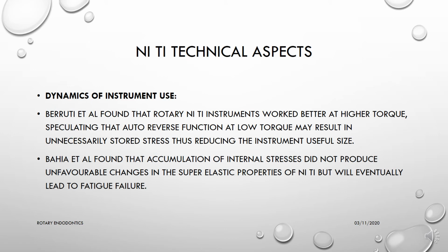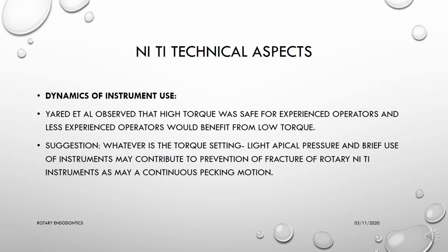Berruti et al. found that rotary NiTi files worked better at higher torque, speculating that the auto reverse function at low torque may result in unnecessarily stored stresses, thus reducing the instrument's useful life. Bahia et al. found that accumulation of internal stresses did not produce unfavorable changes in the superelastic properties of NiTi, but will eventually lead to fatigue failure.